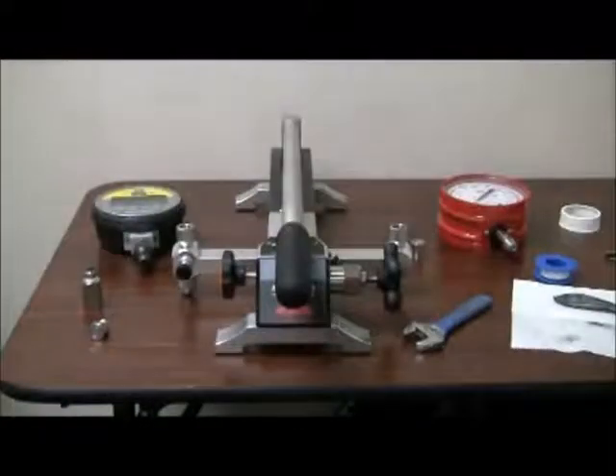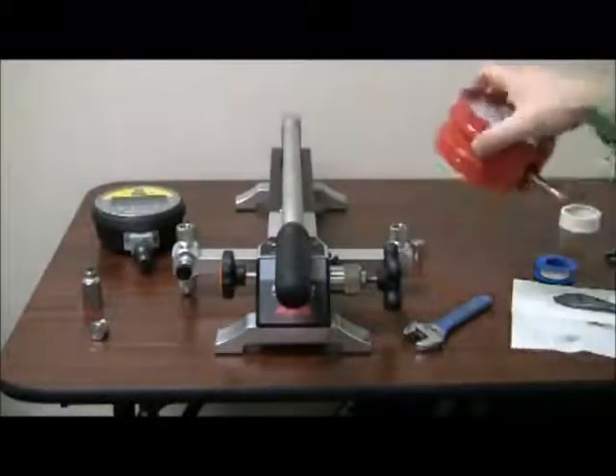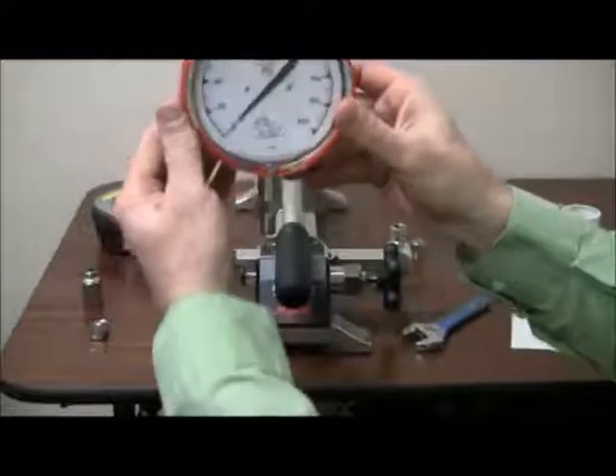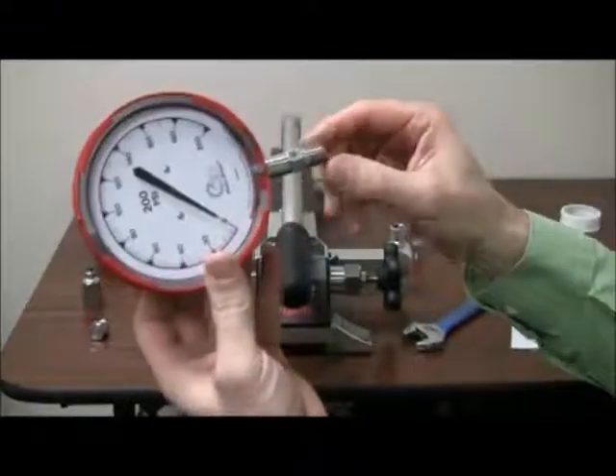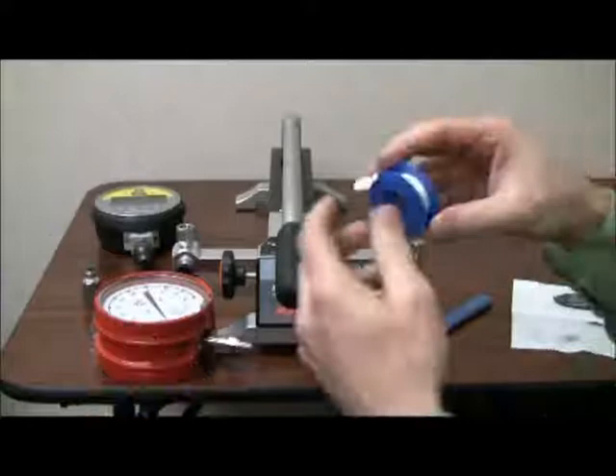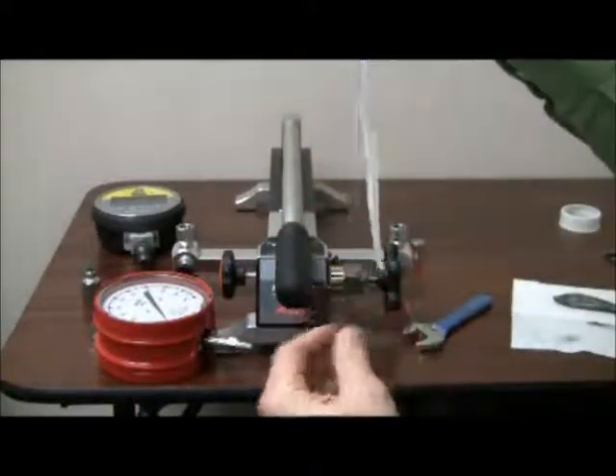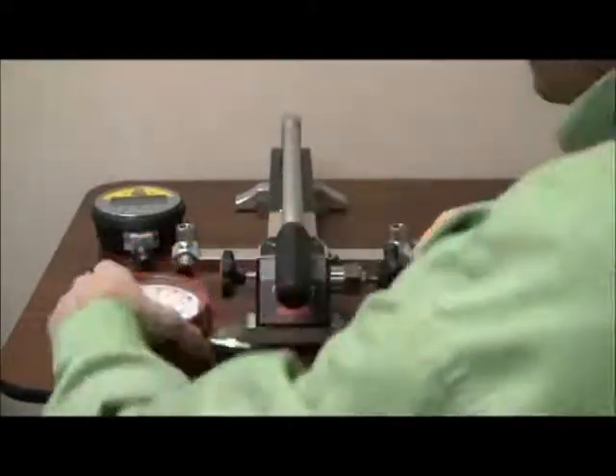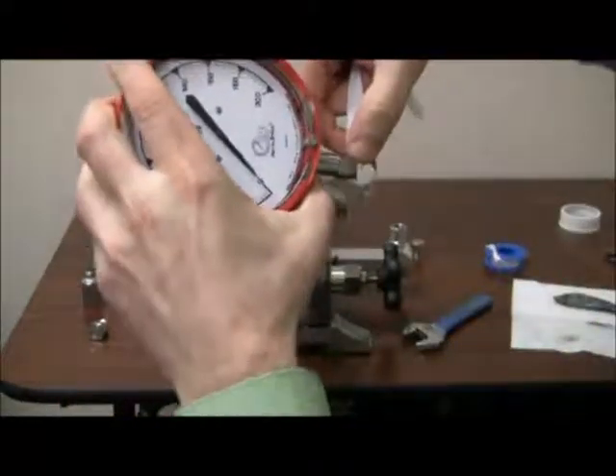Because we have stainless steel fittings, we're going to take some extra precautions today on installing a gauge. Make sure the threads are clean. I'm going to unroll 6 inches of Teflon tape. We'll wrap them in a clockwise direction around the fitting, ensuring a nice tight wrap.